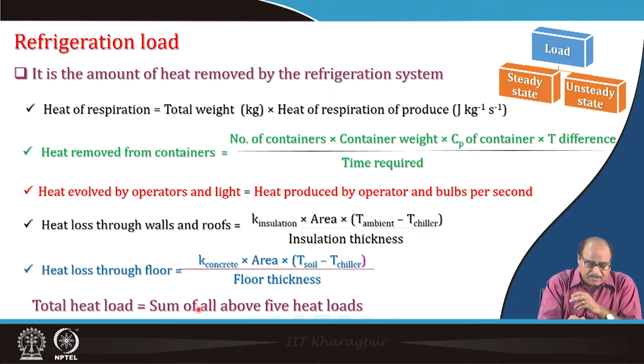Finally, the heat loss through the floor is calculated by K of the concrete multiplied by area, multiplied by T soil minus T chiller, divided by floor thickness. The total heat load capacity will be the sum of all these five loads.